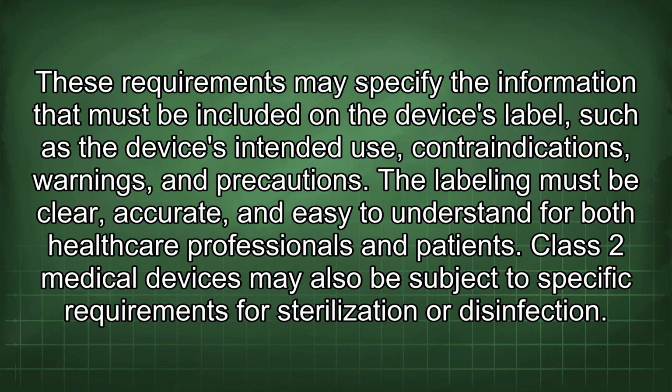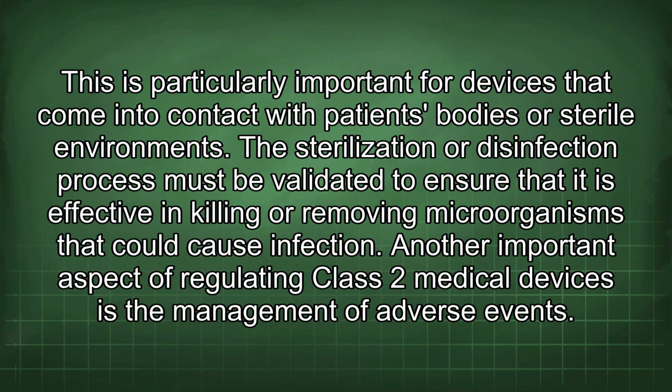Class II medical devices may also be subject to specific requirements for sterilization or disinfection. This is particularly important for devices that come into contact with patients' bodies or sterile environments. The sterilization or disinfection process must be validated to ensure that it is effective in killing or removing microorganisms that could cause infection.